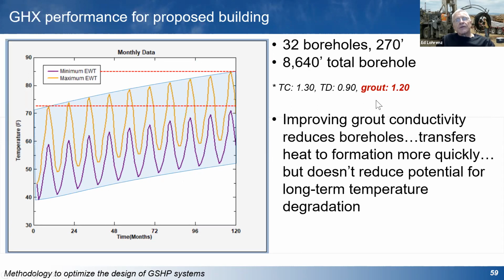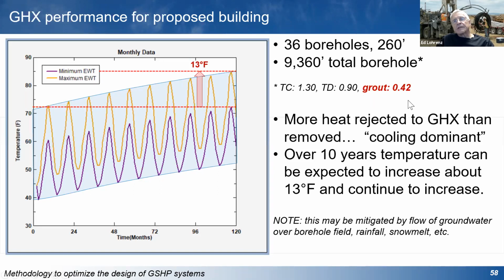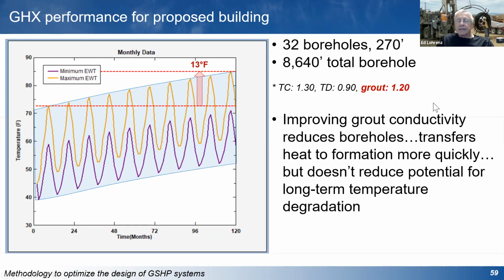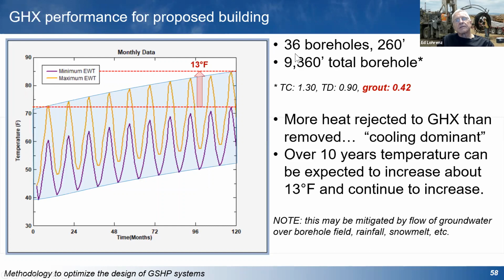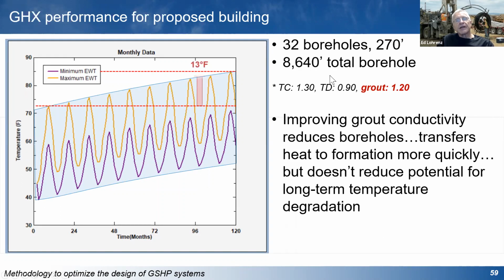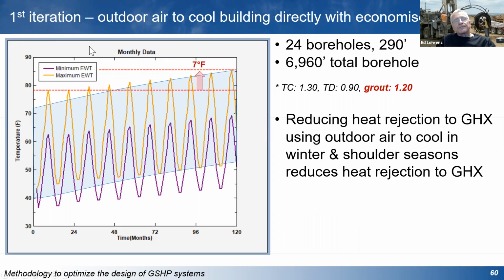So by increasing the conductivity of the grout from 0.42 and getting enhanced grout into the system, we're able to reduce the number of boreholes from 36 down to 32 and knock off about 1,000 feet of drilling. So looking at the detailed borehole design, the borehole configuration and those kinds of things can help further reduce the size and the cost of the borehole field. Looking at what happens once we start modifying the building loads, in this case by using outdoor air to cool the building, we're down to 24 boreholes, 6,900 feet of borehole if we use thermally enhanced grout.